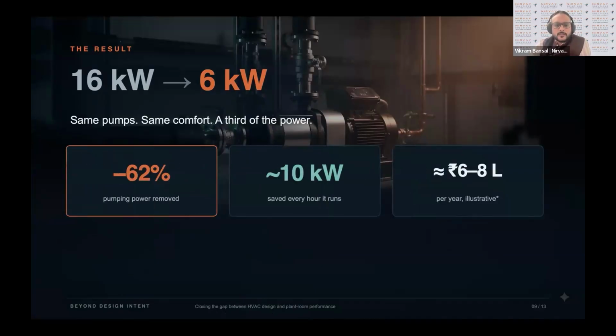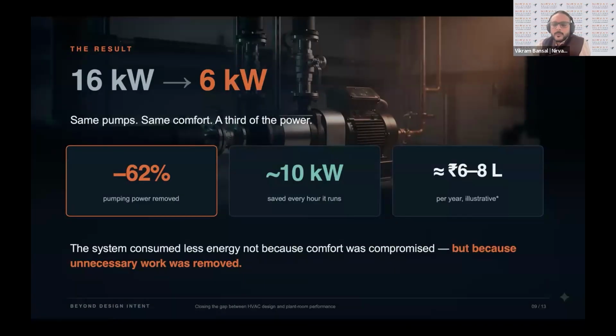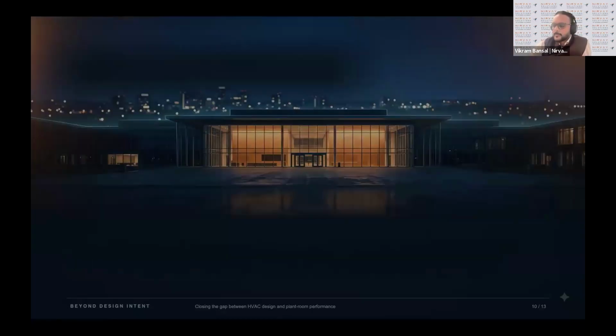a 62% reduction in the pumping power, almost 10 kilowatt of power saved, and 6 to 8 lakh saving for the client. The system consumed very little energy, but no comfort was compromised because unnecessary work was removed from the system.